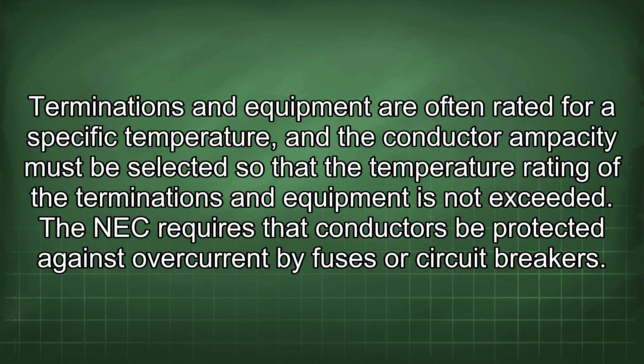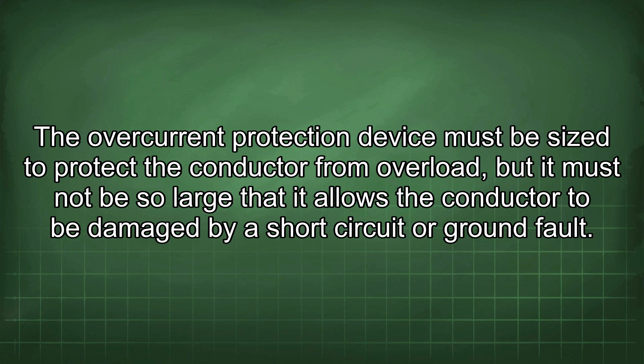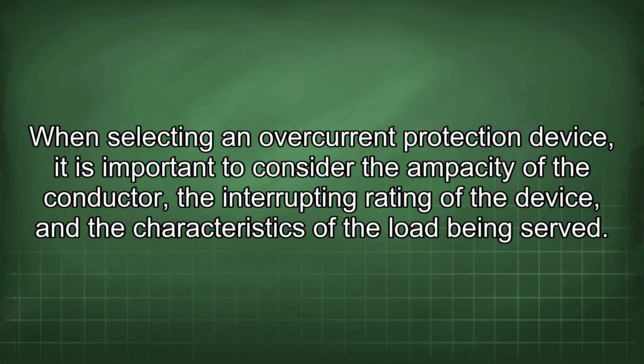The NEC requires that conductors be protected against overcurrent by fuses or circuit breakers. The overcurrent protection device must be sized to protect the conductor from overload, but it must not be so large that it allows the conductor to be damaged by a short circuit or ground fault. When selecting an overcurrent protection device, it is important to consider the ampacity of the conductor, the interrupting rating of the device, and the characteristics of the load being served.